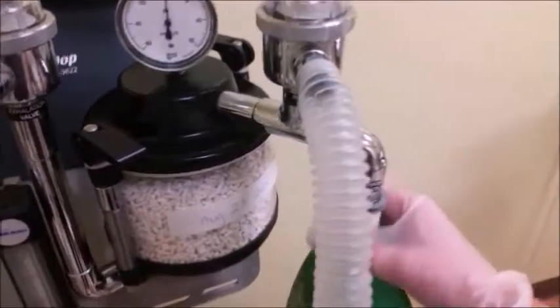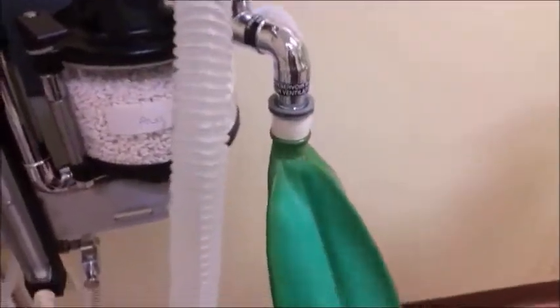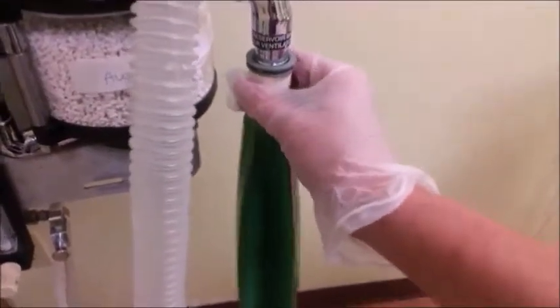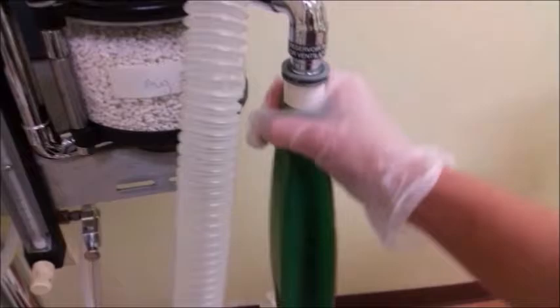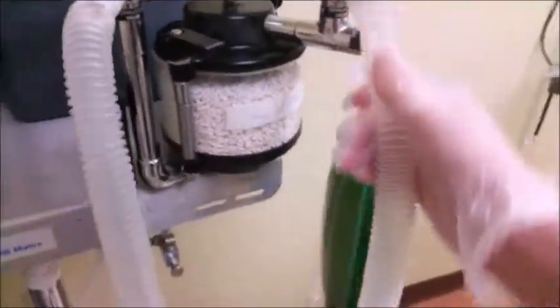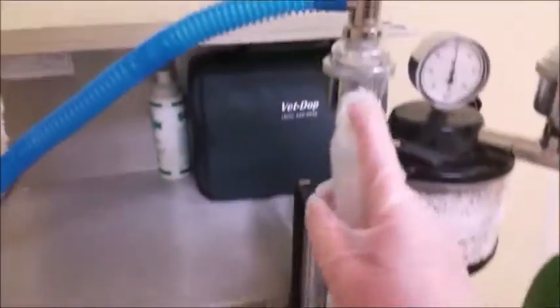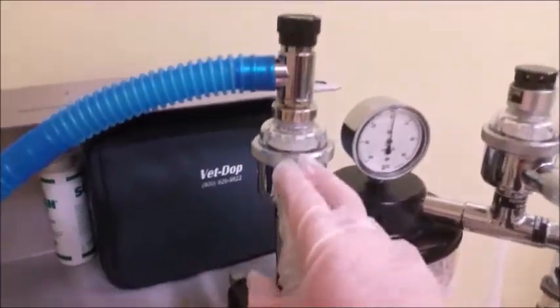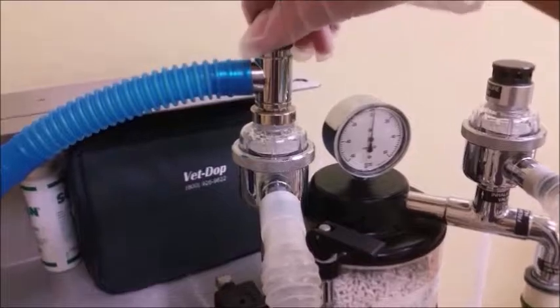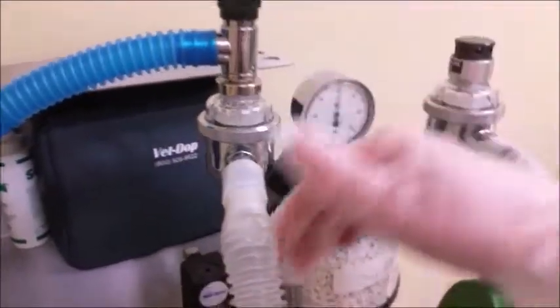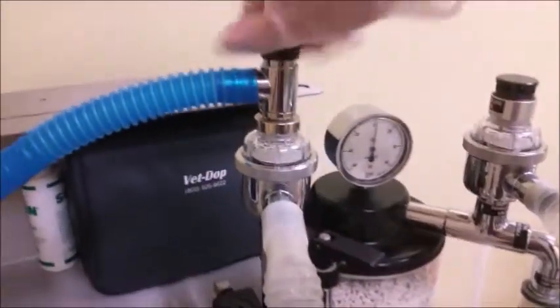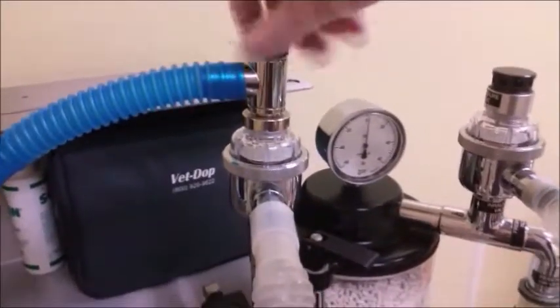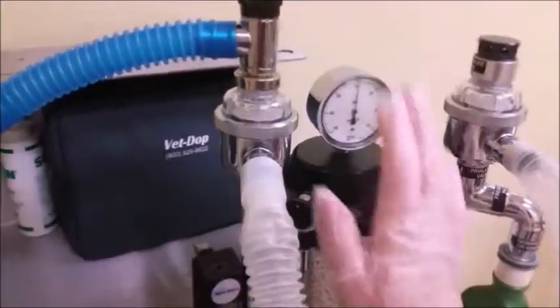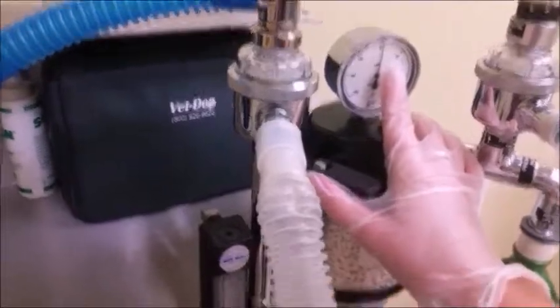Then comes our unidirectional inhalation valve. Any excess gases will fill into our reservoir bag. This bag is also handy if we need to do manual ventilation and ventilate the patient. Inhaled gases then come through our corrugated Y plastic tubing, and exhaled gases go to this side, to our unidirectional exhalation valve. We then have our pop-off valve, which typically for a rebreathing system would be open to allow pressures to move through. If we are to close our pop-off valve, for example, for manual ventilation, we do need to take care that 20 centimeters of H2O is not exceeded on our manometer.